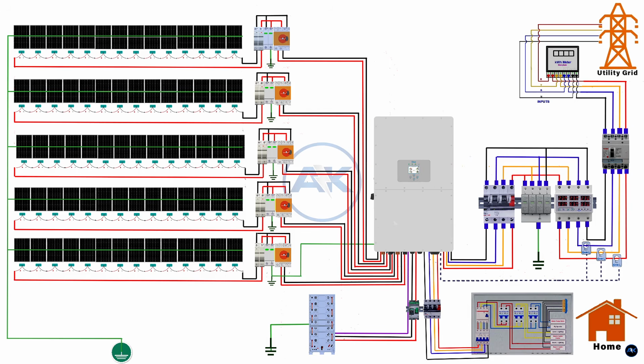Conclusion and results. Suggestions. So, after planning, mounting, wiring, and programming, what were the final results? Let's look at the monitoring. On this sunny day, the 42 kilowatts of solar is producing peak power. The company's loads are running directly off that solar. The excess is quietly charging this 60 kilowatt-hour battery bank. And most importantly, the grid import is hovering near zero. The CT sensors and our configuration are doing their job perfectly. Zero export, maximum self-consumption.